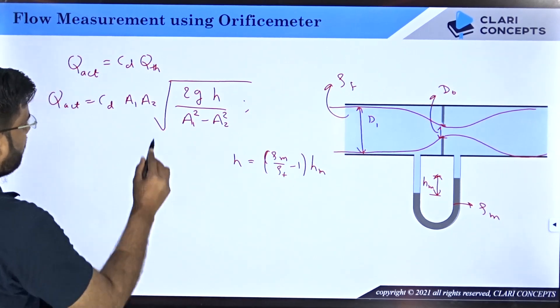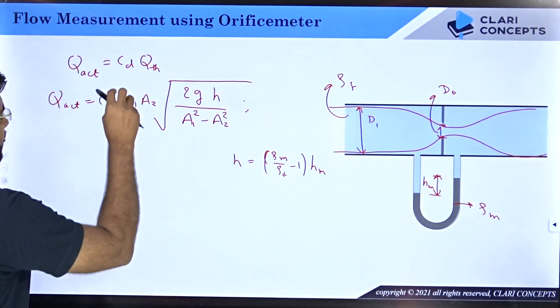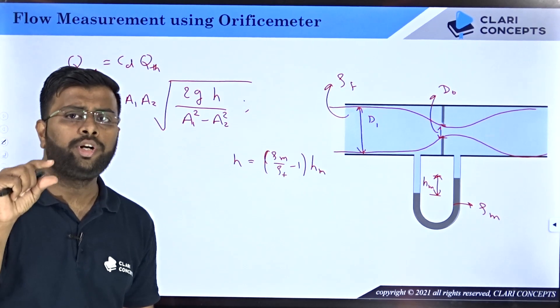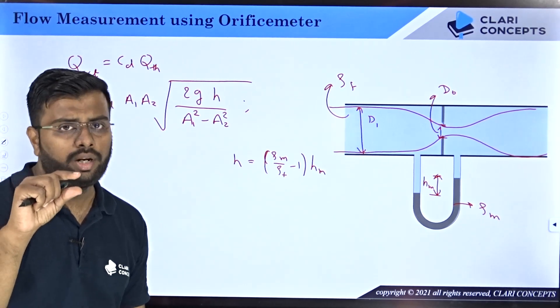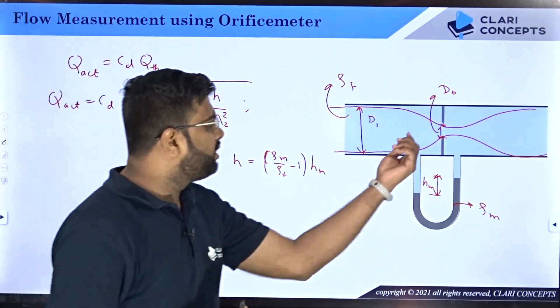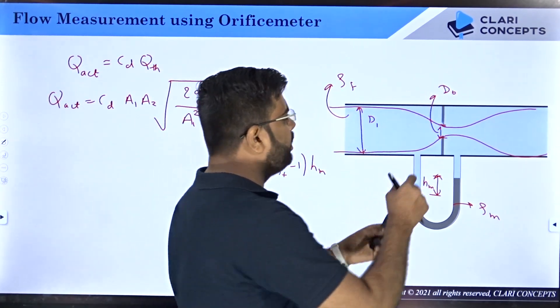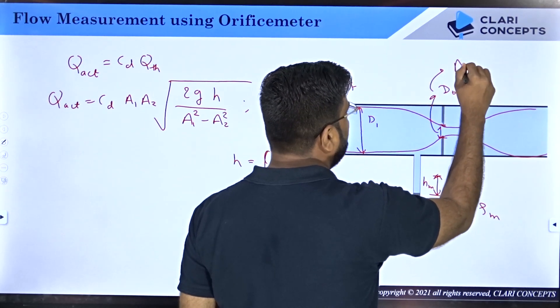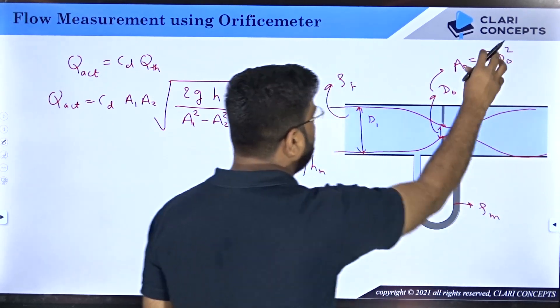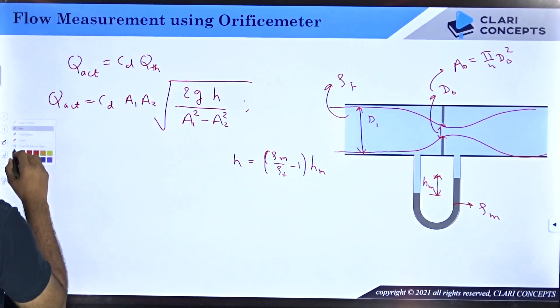A_1 was the main diameter or main area of the pipe. What was A_2? A_2 was the area corresponding to the throat section of the venturimeter. But here there is no throat. In case of venturimeter, throat section was a minimal area. Here the minimal area is d_o, and corresponding to d_o you will have area called orifice area which is π/4 d_o square. So instead of A_2, in case of orifice what you will have is A_o, where A_o is the cross-sectional area of orifice.